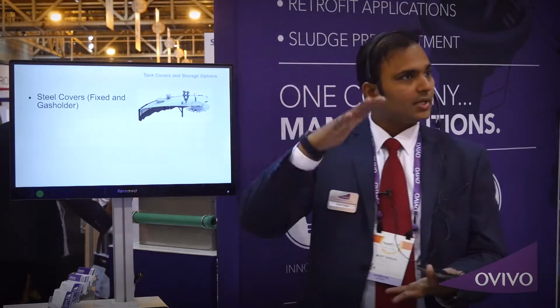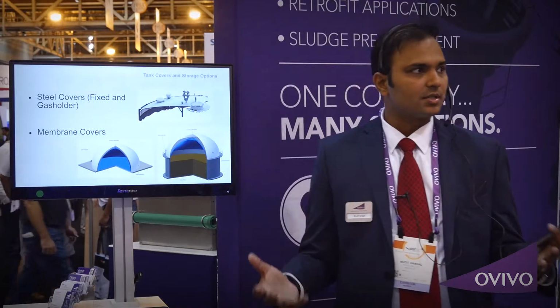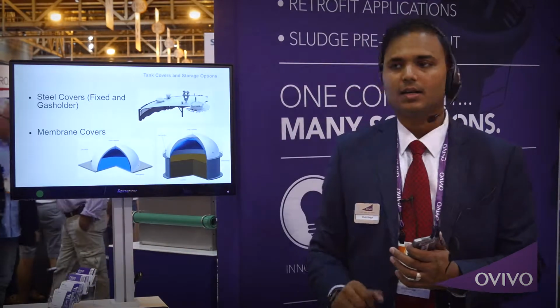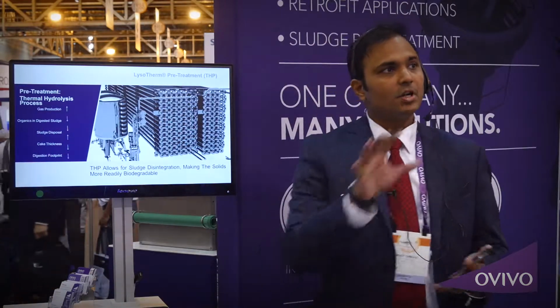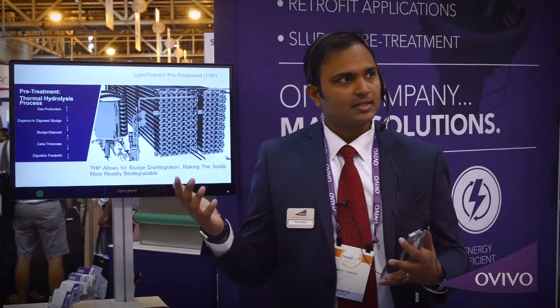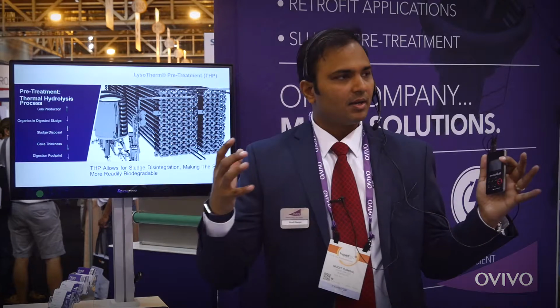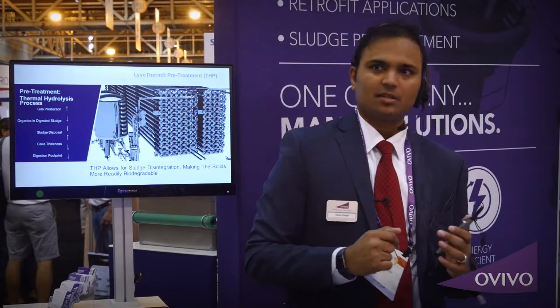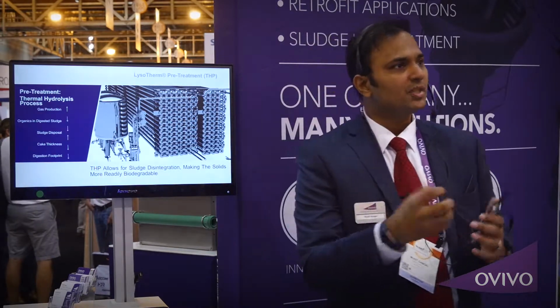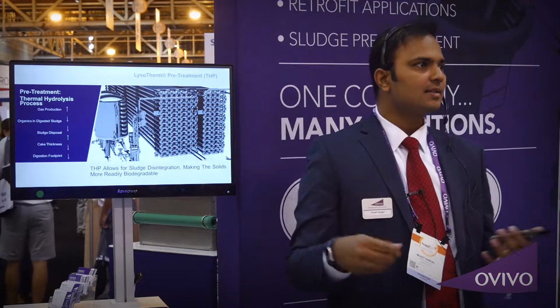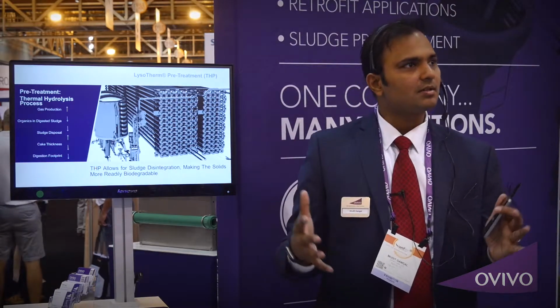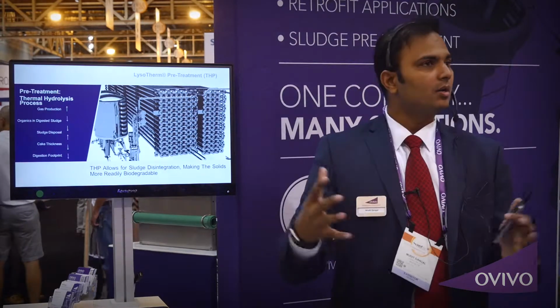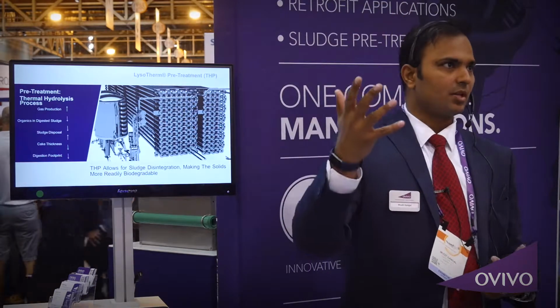As we were talking about the gas storage part, there are the steel covers, which are fixed or floating in nature, or you could use membrane gas holders either on top of the digester or in separate gas storage areas. And when we're talking about the enhancement of digestion, this is where different processes come in. There's the pre-treatment by thermal hydrolysis, which is essentially a big pressure cooker for sludge. What you're trying to do is essentially crack open the cells due to this high temperature and pressure, so that when that sludge hits your digesters, it's easier to digest, and hence your retention time in the anaerobic digestion is a lot lower, or within the same volume you have much higher volatile destruction, much higher gas production.